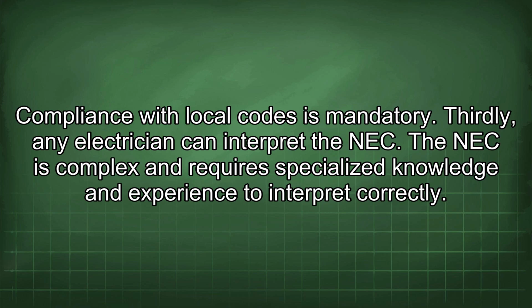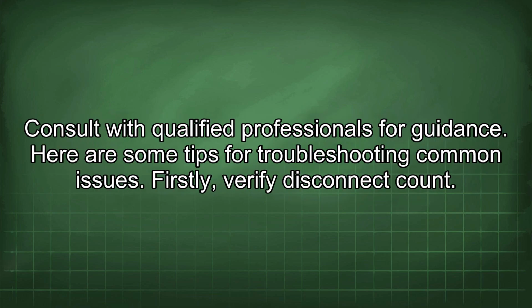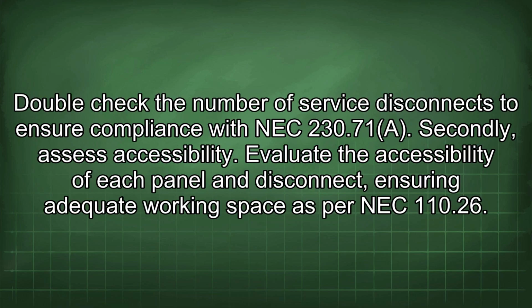Thirdly, any electrician can interpret the NEC. The NEC is complex and requires specialized knowledge and experience to interpret correctly. Consult with qualified professionals for guidance. Here are some tips for troubleshooting common issues. Firstly, verify disconnect count. Double-check the number of service disconnects to ensure compliance with NEC 230.71(A). Secondly, assess accessibility. Evaluate the accessibility of each panel and disconnect, ensuring adequate working space as per NEC 110.26.